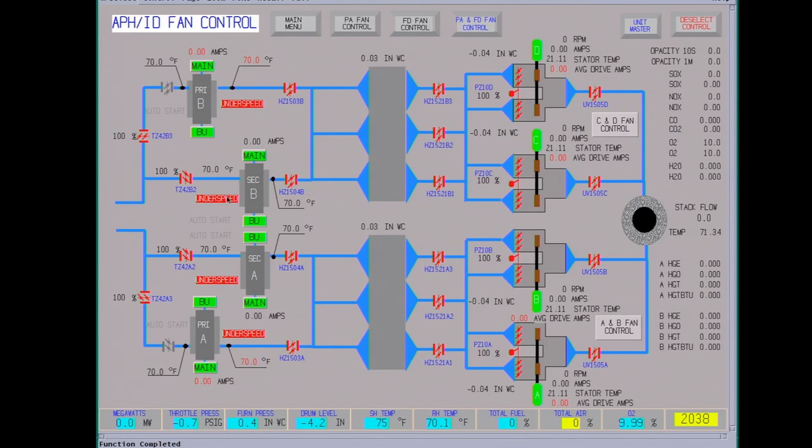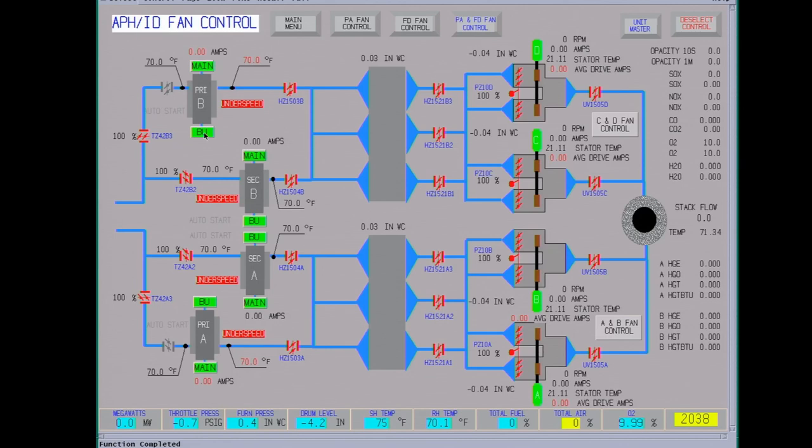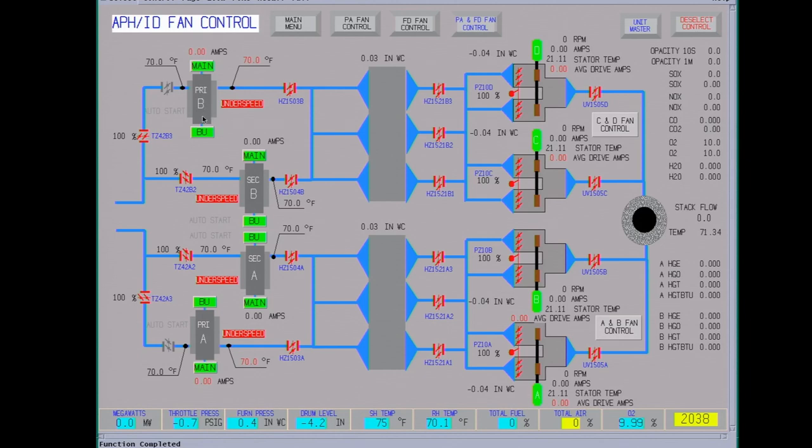We're gonna start the air preheaters. There's two motors on it: you have a backup drive and then the main drive. Backup drive's a little slower, this is for emergency use in case you lose your main drive. You don't want the wheels exposed to the hot flue gas too long or it will warp them.